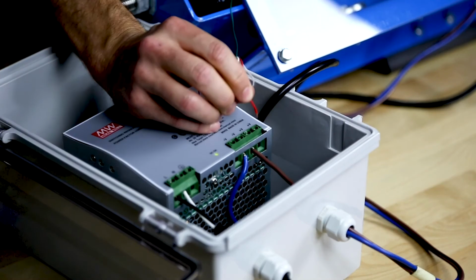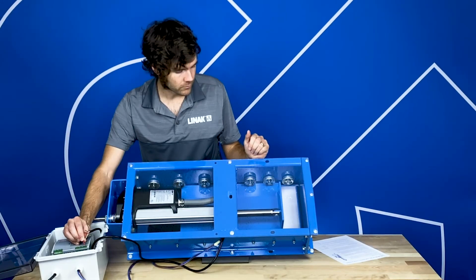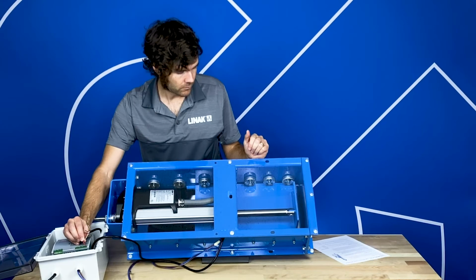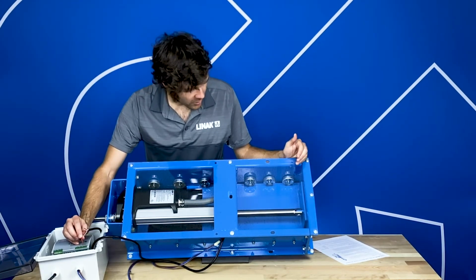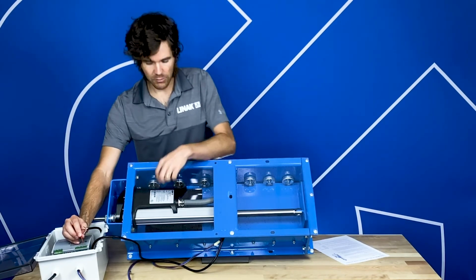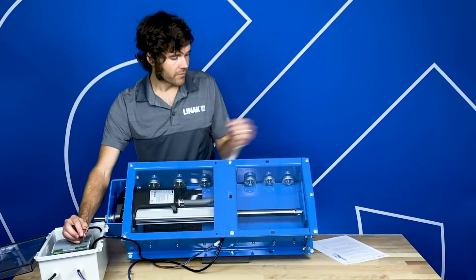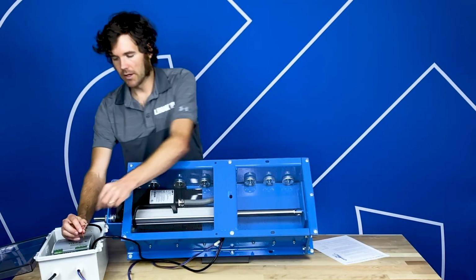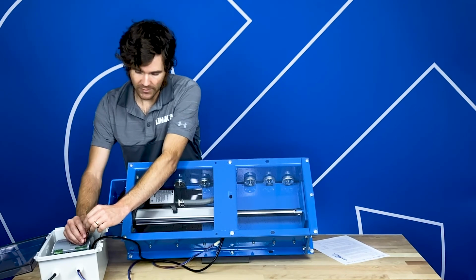And then we're going to run to that position again. This time you won't see that hard collision. So now the valve is fully shut. It has learned that position, and the actuator will be giving an end of stroke signal on one of the end of stroke wires at this point. And the feedback is scaled as well.